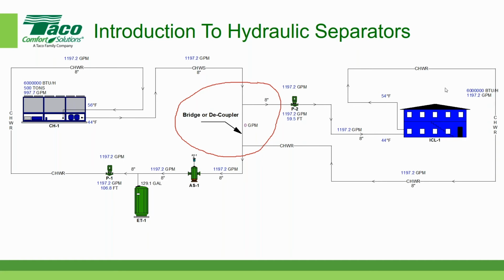The very first one we'll take a look at: let's assume that the primary loop, and we're going to round these values off, is 1,200 gallons per minute. So all of our discussion in this first part of the presentation will be based on 1,200 gallons per minute. So let's assume that our primary loop is delivering 1,200 gallons per minute. It goes around the corner right here. And for now, initially, we're going to say that the secondary loop pump is off, and we're not pumping any water in the secondary loop.